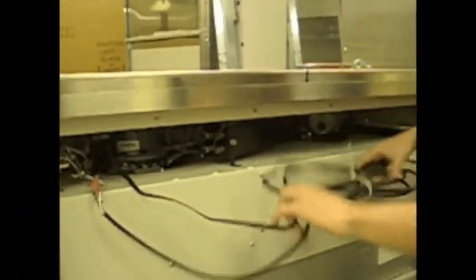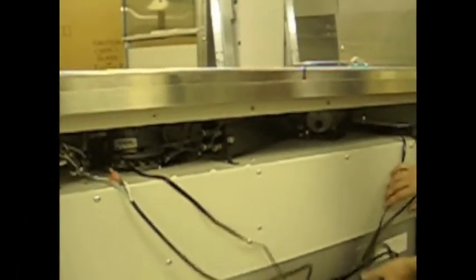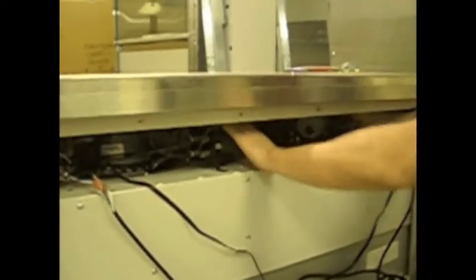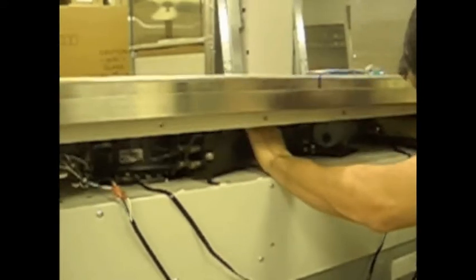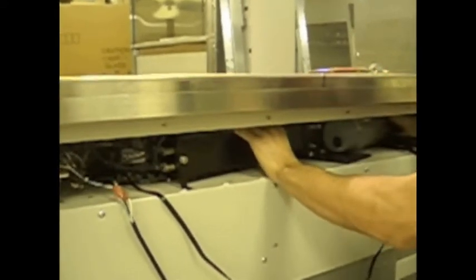Rest electrical wires and hydraulic lines carefully along the face of the plenum as you begin to slide the lift system housing out of the unit. The system may have to be shifted to the left to clear the plenum bracket along the side of the unit.